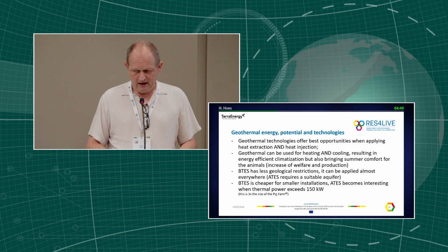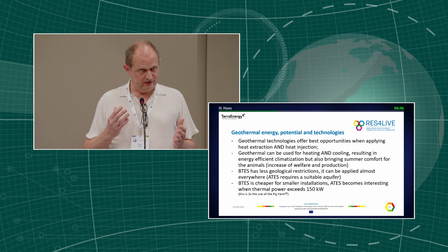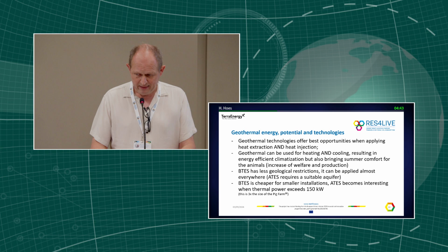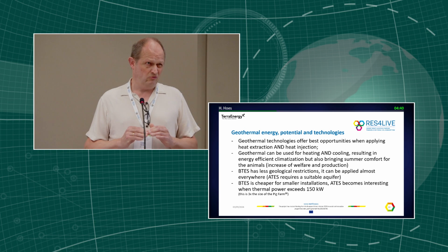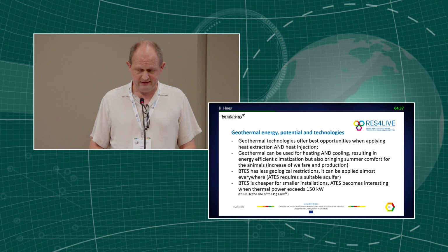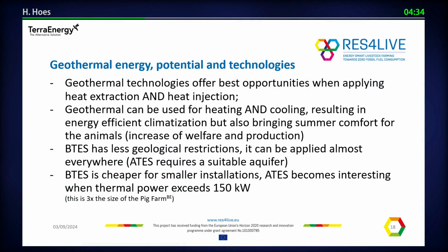I want to say something of the difference between ATES and BTES, the aquifer system and the borehole system. The BTES system has less geological restrictions. You can almost use it everywhere. ATES is more complex and requires a suitable aquifer. And typically, BTES is cheaper for small installations, and ATES becomes interesting when the thermal power exceeds, that's our experience, let's say 100 to 150 kilowatt, let's say 150 kilowatt. This is 3 times the size of the Belgian pig farm in this example. So it's certainly not possible to use it at small farms.